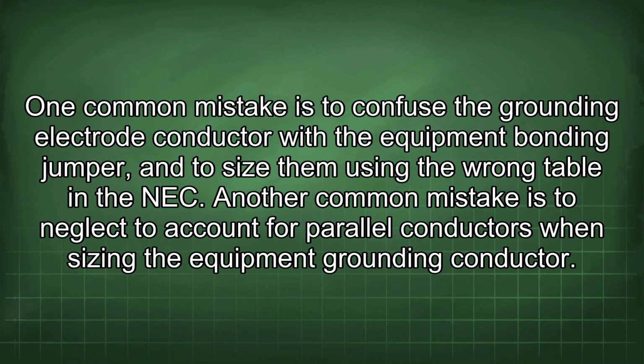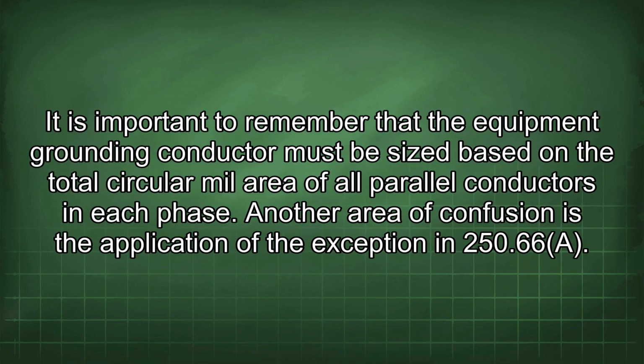One common mistake is to confuse the grounding electrode conductor with the equipment bonding jumper and to size them using the wrong table in the NEC. Another common mistake is to neglect to account for parallel conductors when sizing the equipment grounding conductor. It is important to remember that the equipment grounding conductor must be sized based on the total circular mil area of all parallel conductors in each phase.